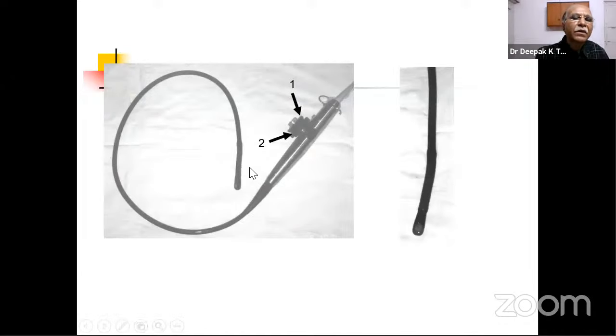And this is the probe. It is a gastroscope, endoscope, where the transducer is housed at its tip. And there is a handle here. Handle has got two knobs, circular knobs, the inner large wheel and the outer smaller wheel. And these are used to anteflex and retroflex the tip of the probe or lateral flexion of the probe. In addition, there are two small buttons here which you may not see very clearly, but these are used to rotate the ultrasound beam from 0 degrees to 180 degrees. So if you have at 0 degrees, you get the transverse section, at 90 degrees, you will get the longitudinal section, and you will get several oblique sections in between 0 degrees and 90 degrees and 90 degrees to 180 degrees. And this is the close-up of the probe.